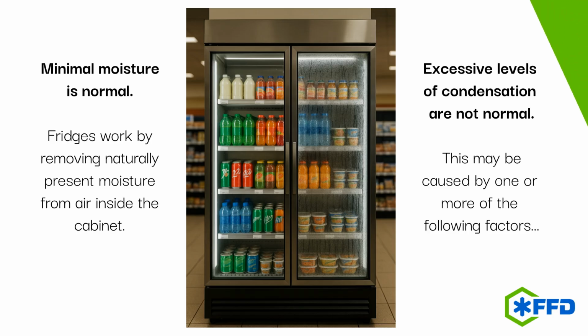A small amount of moisture is normal, as refrigeration works by drawing moisture from the air in the refrigerated cabinet. Excess moisture will collect in the bottom of the cabinet at the drainage point and egress via the small drain tube to the evaporator tray or drain pan. However, excessive levels of condensation are not normal and may be caused by one or more of the following factors.